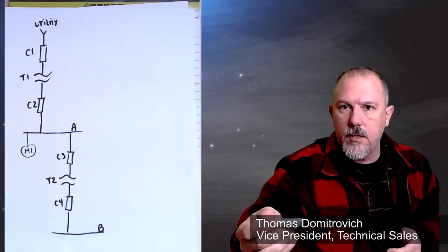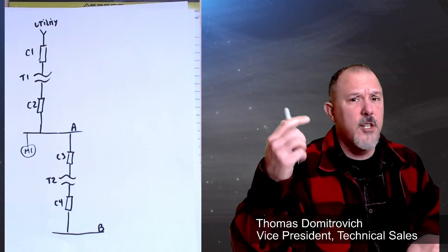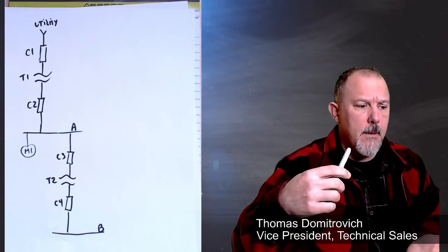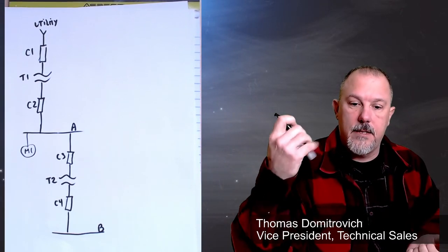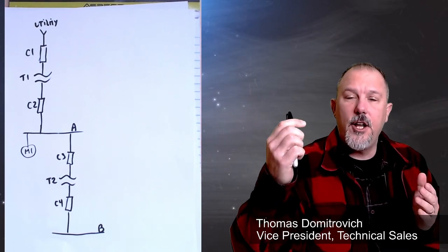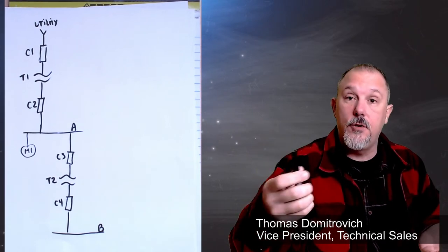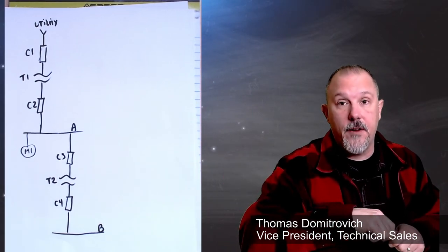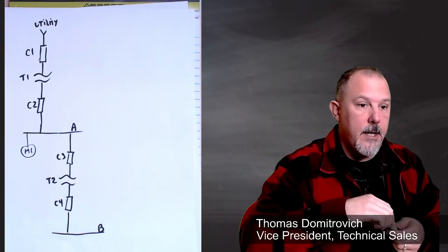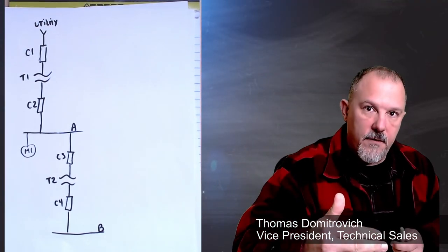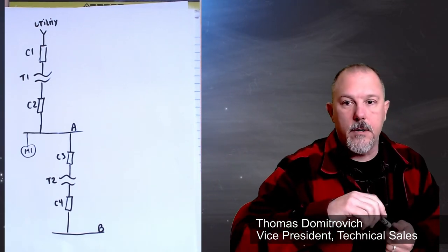Impedances of bus work, you know, the heavy copper bus that you would have inside of a panel board or switch gear, is insignificant. You could try to model it. You could put the impedances in and run the analysis, and you'll see it does not have a very large impact on available fault currents. Because remember, we want to be in the ballpark, and we're going to be conservative in our assumptions to get a maximum available fault current.